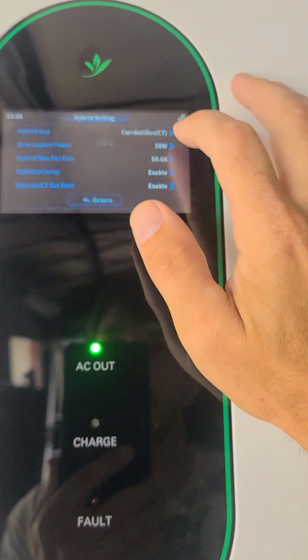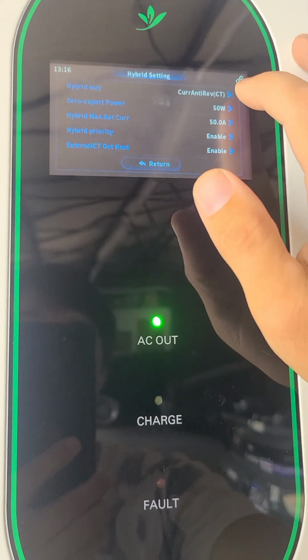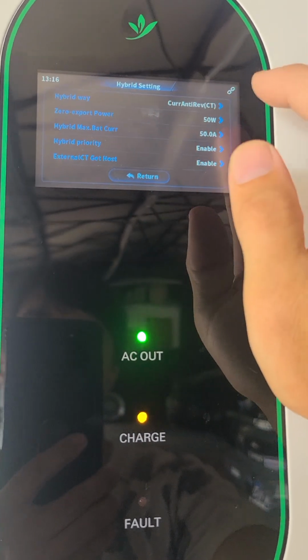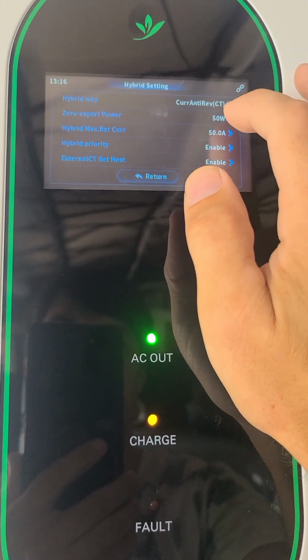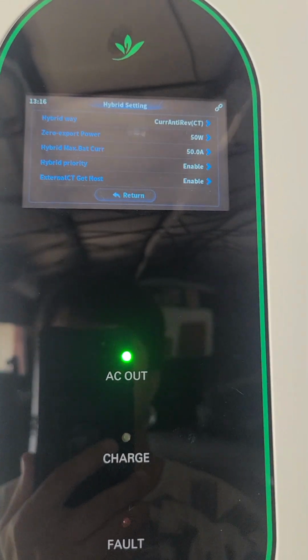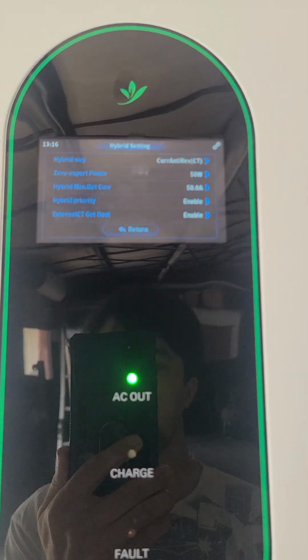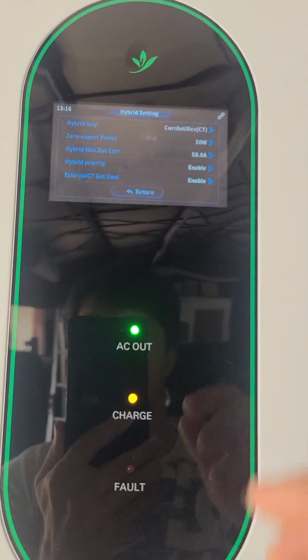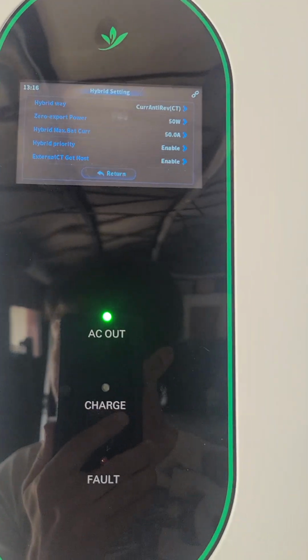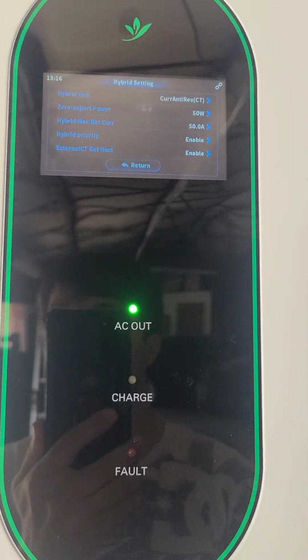So here's where we change current anti-reverse CT. We want that to be the setting for zero export. Zero export power is 50 watts. Again, like I said, this is our reserve power, so we do not backfeed the grid. The default setting was 25. Some people say you need 100. I think 50 is okay.